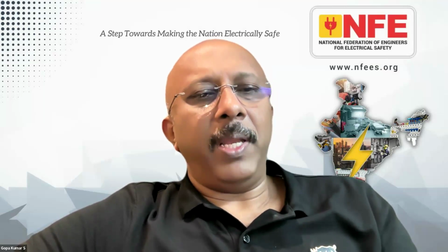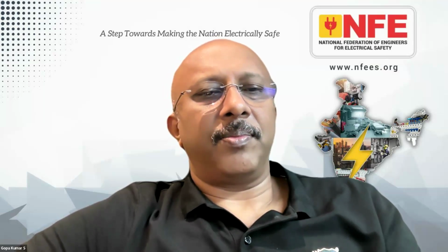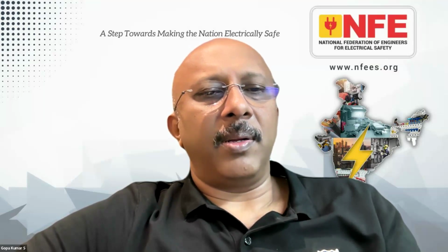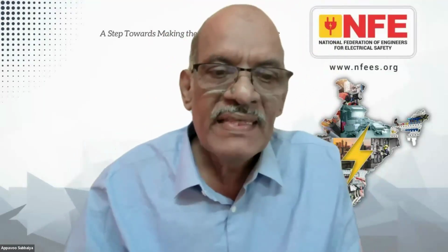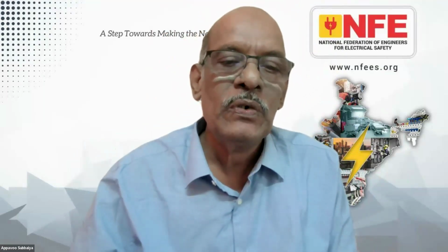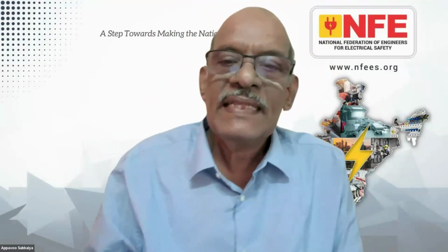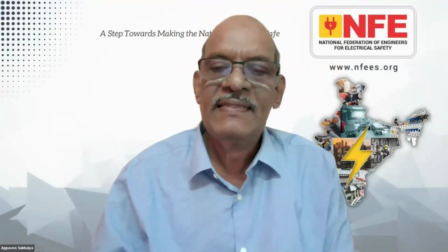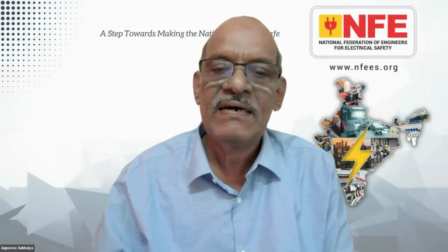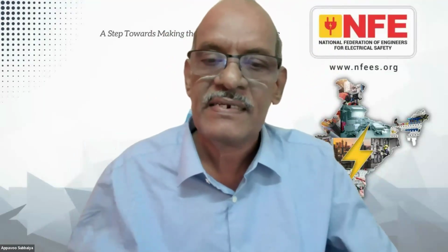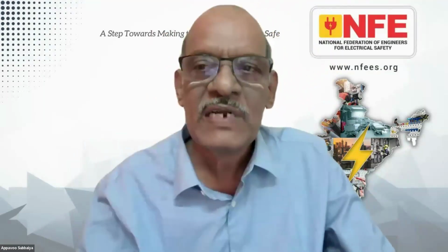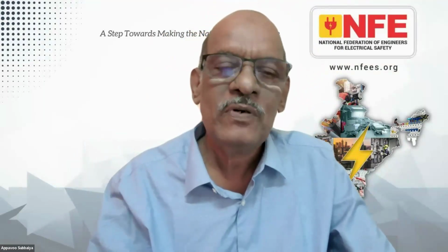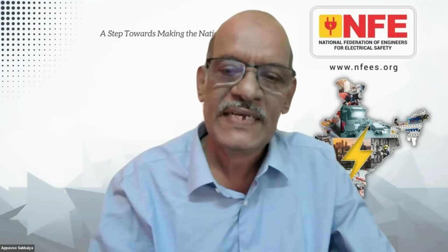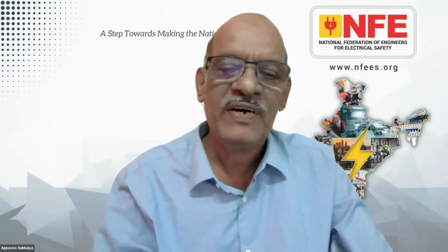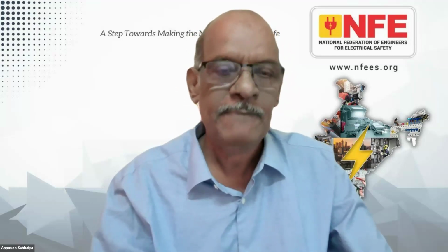So, Mr. Appavoo, do you have any points to add here? You are on mute, sir. Yes, sir. As Krish opined, it's a thing that we are yet to follow, because the main panel, whether it is a generator, standby generator set or a transformer, we have transformers as per IS up to 2500 kVA. This is permissible for any LV distribution arrangement.